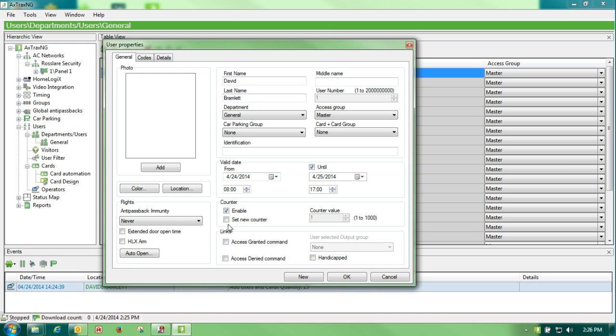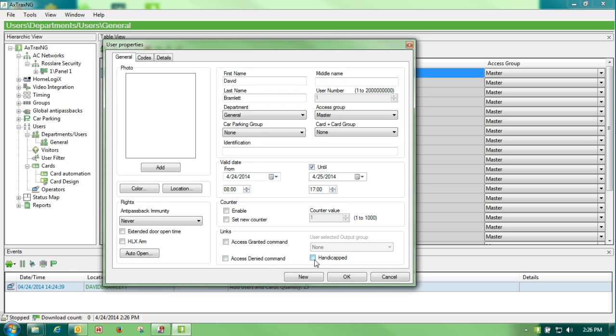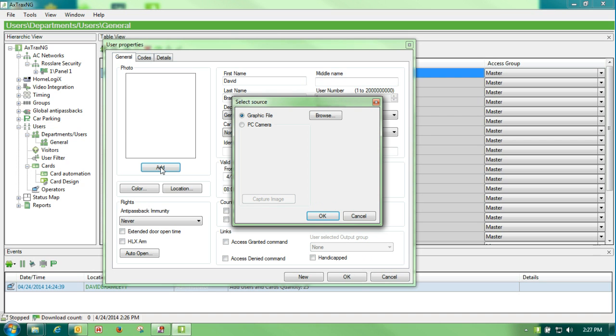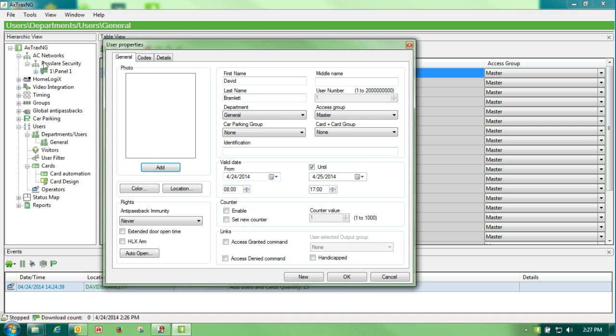You can do the same thing with the counter. If you want to enable counter and you want to give this person two swipes, three swipes, whatever it may be, you can do it there. Access granted commands, we'll talk about those. Those will be used in AC links that we want something specific to happen if this badge is swiped. And we can use access denied also. We can classify this person as a handicap. And we can also put this person in an output group which most often is used for elevator control. You can add a photo to anybody so that when they swipe their badge, we can turn it on under the panels themselves and we can turn it on and have a pop-up screen each time someone comes in.